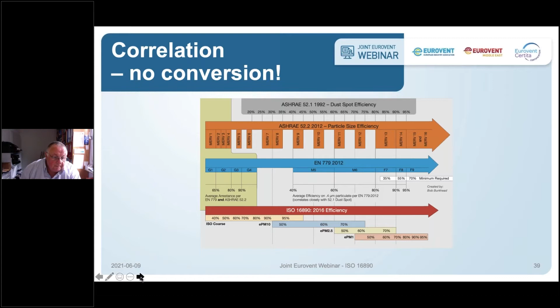So let's now come to a practical exercise: how to select a filter according to outdoor air quality categories and according to the desired supply air you want to have in the room. The base of all of that is, first, a classification of the outdoor air quality. That's the air quality on site where the building is located. And there are 3 outdoor air qualities defined here.